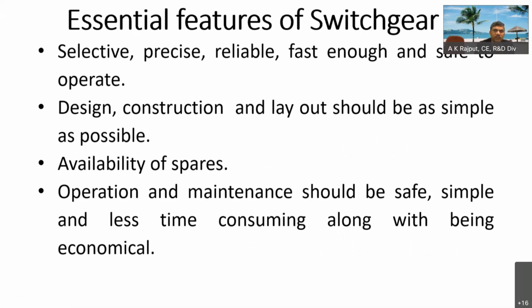So what are the essential features of the switchgear? When we select the switchgear or any product for use, we have to see that it has the selectivity feature. It is precise in operation. It is reliable, fast enough or swift enough, and safe to operate. As I told in my opening remark also, while operating, sometimes they burst and create havoc, even fatal accidents. So we should avoid that, and we should have a proper design review and simulation testing before deploying them in the field.